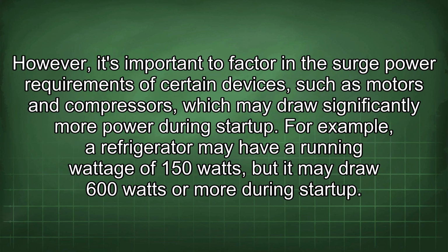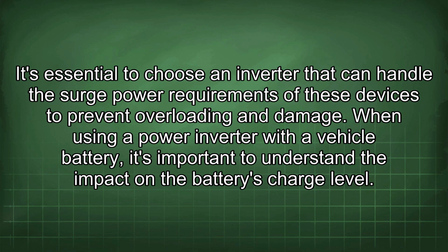However, it's important to factor in the surge power requirements of certain devices, such as motors and compressors, which may draw significantly more power during startup. For example, a refrigerator may have a running wattage of 150 watts, but it may draw 600 watts or more during startup. It's essential to choose an inverter that can handle the surge power requirements of these devices to prevent overloading and damage.